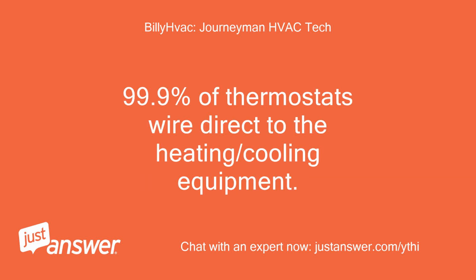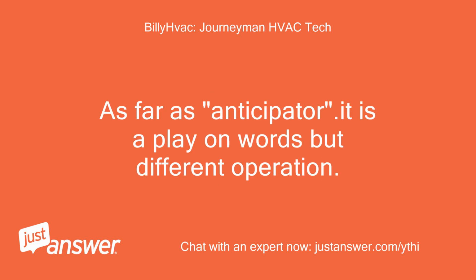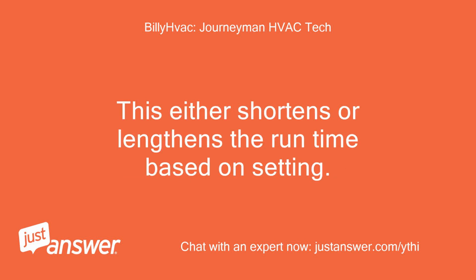99.9% of thermostats wire direct to the heating/cooling equipment. Yours does not. The equipment wires to the interface and thermostat, then to interface. As far as Anticipator, it is a play on words but different operation. Anticipator is used while running to anticipate shutdown. This either shortens or lengthens the runtime based on setting.